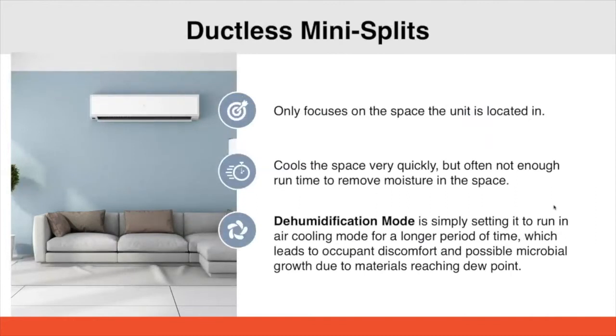And ductless mini splits, most of them that I have seen, we talked about sensible heat ratios at the last webinar. They're very effective at getting to that sensible temperature, but again, not a lot of latent removal by the ductless mini splits. They are designed to condition smaller spaces to get to that temperature, and most of their dehumidification modes are based on a timer situation, and you can quickly overcool a space. So you have to be very, very careful when you're using that dehumidification mode on the mini splits.